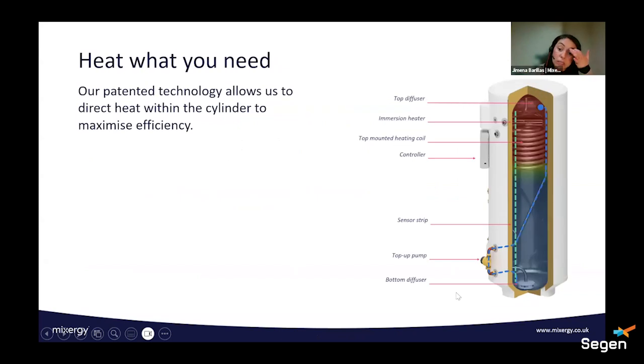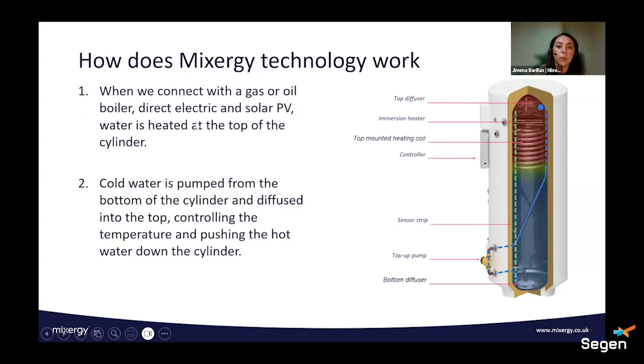Whereas our technology uses this top-up pump where it draws the cold water from the bottom, takes it all the way to the top, and uses this top diffuser to spray a light mist to the heated water. This is because, as you can see here, the coil and the immersion are at the top. So you're heating from the top down using the diffuser, which means that the hot water isn't diluted. It's just immediately heated to the temperature that you want it to be. When you connect it to a gas or oil boiler, direct electric or solar PV, the water is heated from the top of the cylinder.